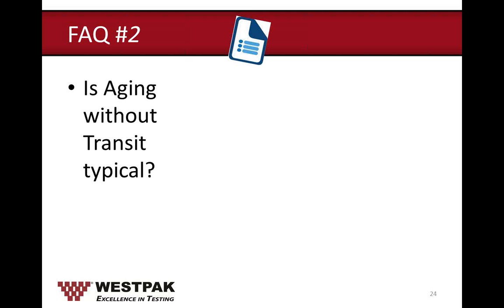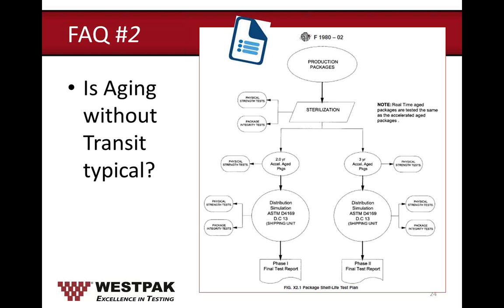The next question: what is the norm — aging without transit, or aging with transit? Our customers are split on this. I mentioned that aging and package performance testing are separate entities according to ISO 11607, but some customers still combine them. This traces back to the 2002 revision of ASTM F1980, which included a flowchart indicating distribution simulation per ASTM D4169 should be conducted after accelerated aging. In the 2007 revision, that flowchart was removed, and some customers started separating aging and transit.